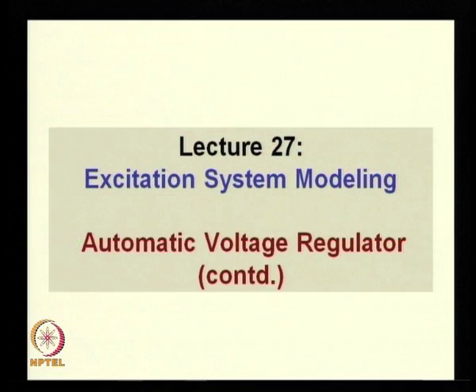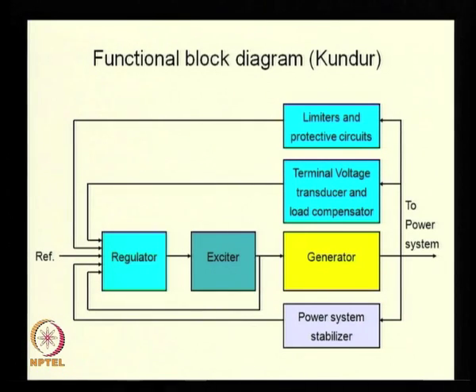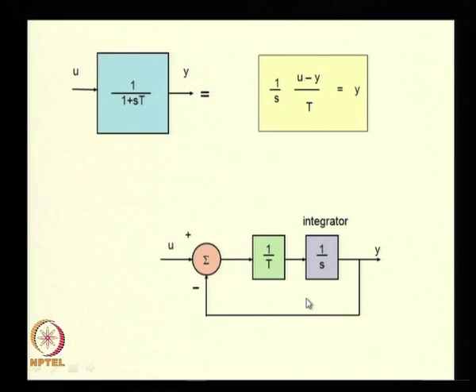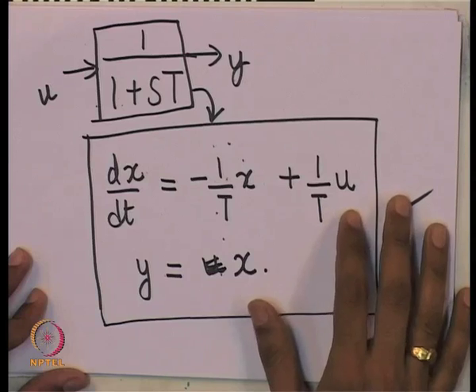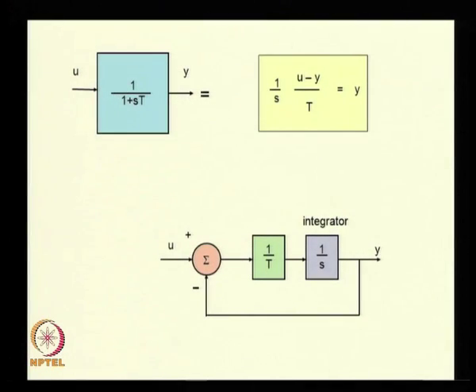Today's lecture is a continuation of our discussion of automatic voltage regulation, focusing on transfer function blocks. The first block pertains to the regulator: a first-order transfer function represented as 1/(1+sT), whose state-space representation can be written immediately. There is no unique state-space representation of a transfer function. You can also add non-linearities to the block diagram — for example, limiters — which we will discuss shortly.